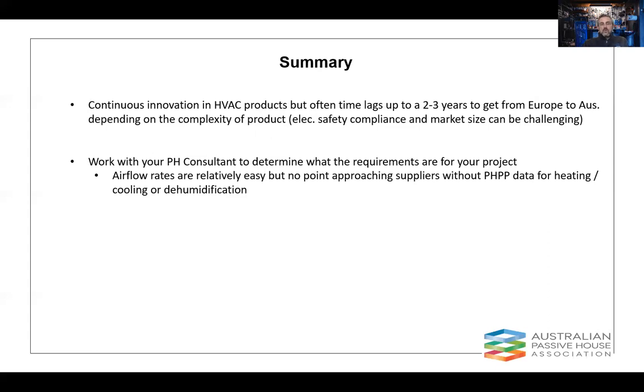What I would also say is work with your passive house consultant to determine what requirements you have for your project on heating and cooling and dehumidification. There's really not a lot of point approaching your MVHR supplier saying I need some dehumidification when we've got no way to understand what that is, because those things are very climate and project specific. The proportion of heating and cooling you need and dehumidification are both climate and project specific attributes. And so without that data, we really can't start to help you with products that might be suitable.